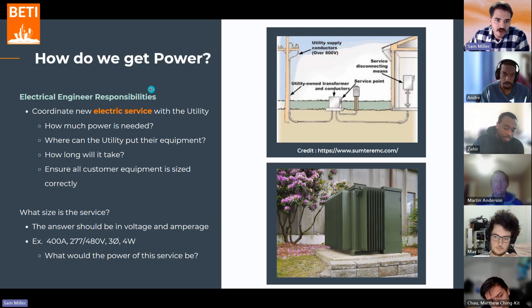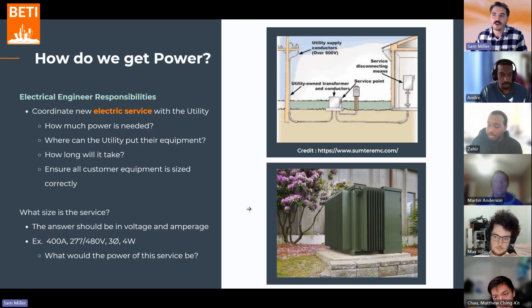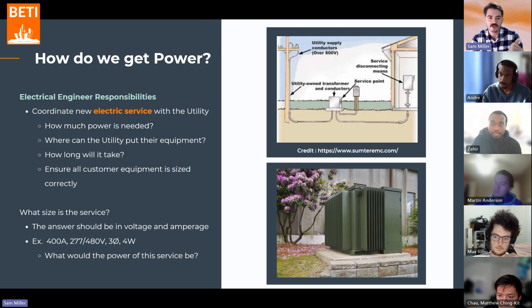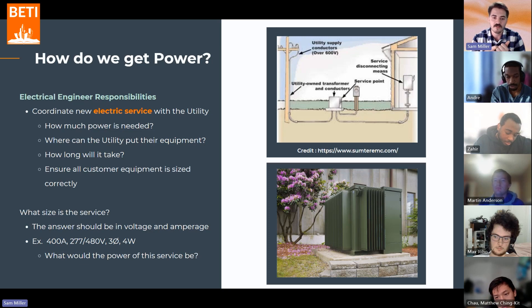When I say electric service, the measurement of an electric service should be in voltage and amperage. Early in my career my boss asked me what the size of the electrical service was and I didn't know how to respond, even with the drawings in front of me. The electric service tells you how much power the customer is getting, and that should come in the form of amperage and voltage. The power equation is: power equals voltage times amperage. If you give voltage and amperage, they can tell how much power there is — but if you just give power, they don't know what the voltage and amperage split is.